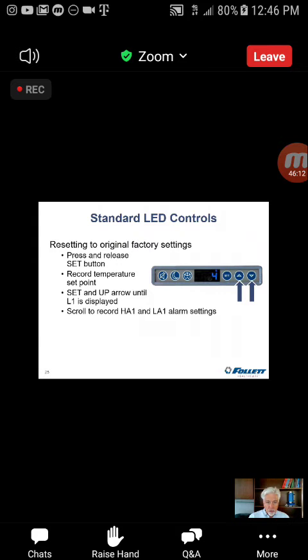So we want to check, we scroll until we see HA1, that is high alarm number 1. And you touch set, and it will show you the current setting. Then you hit set to back out of it. Don't hit an arrow, because if you hit an arrow, it's going to adjust it. Hit set to back out, and then use the arrow to scroll to LA1, low alarm number 1. You hit set, it will show you that value. Then we record both of those. Next thing that we're going to do, because we're still in level 1, is we go to level 2 by going back to the set and the up arrow, the arrow closest to it.